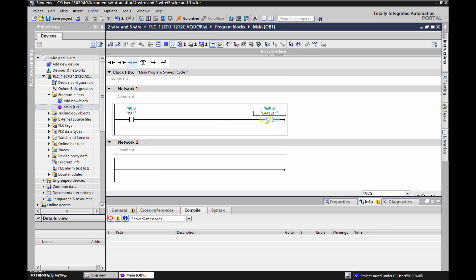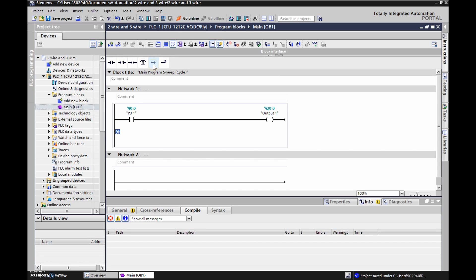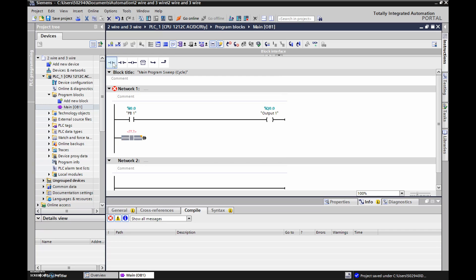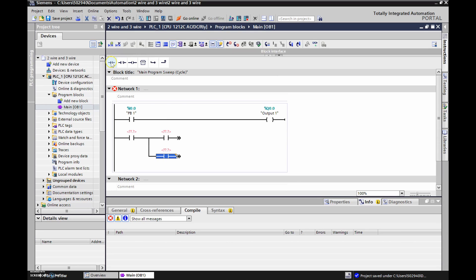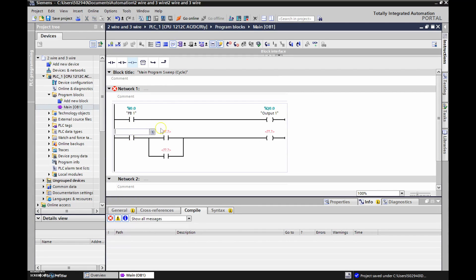We've got our two-wire control. Below that we'll make a three-wire control. We'll add another rung and put in our stop push button, then our start push button, and in parallel with that we're going to add a parallel rung with a holding contact. Then we'll close the branch and add our output. Let's make this input 0.1.